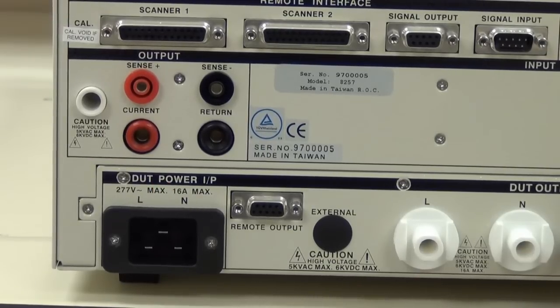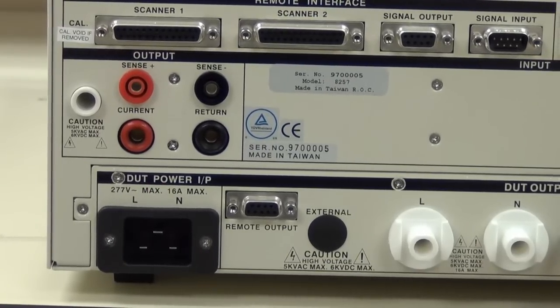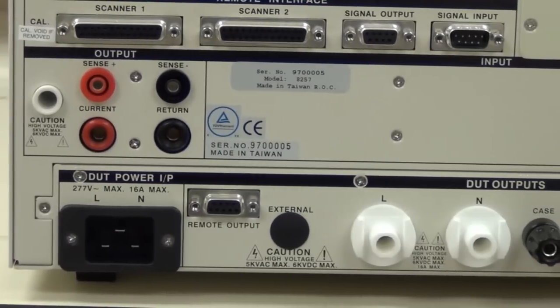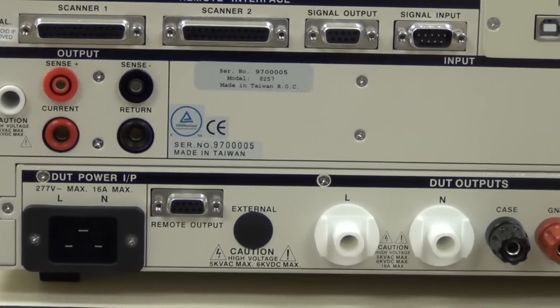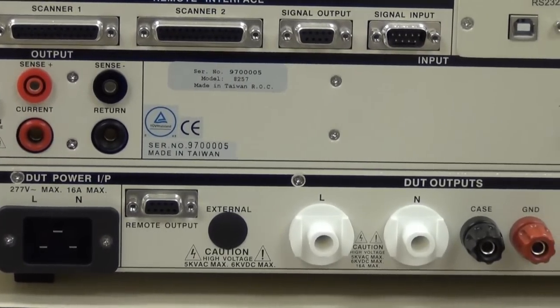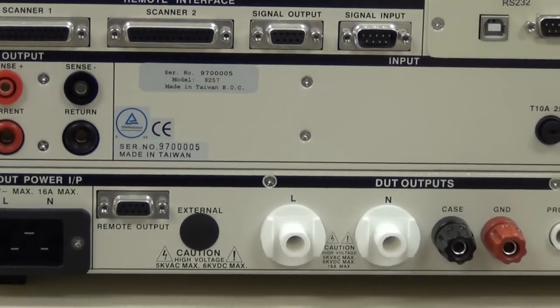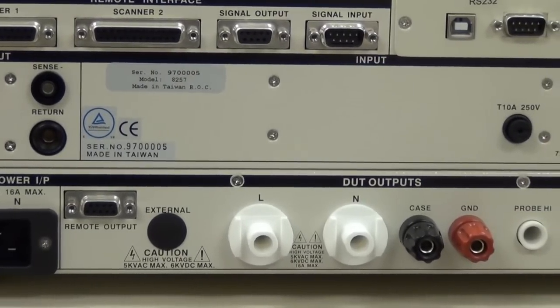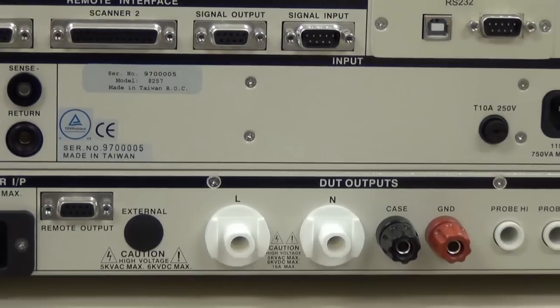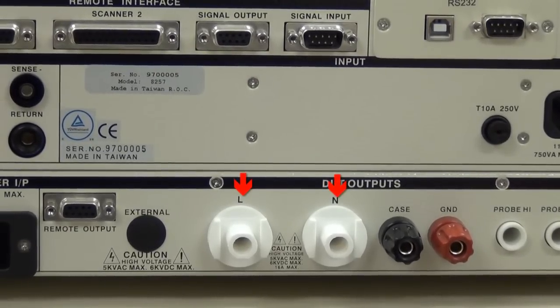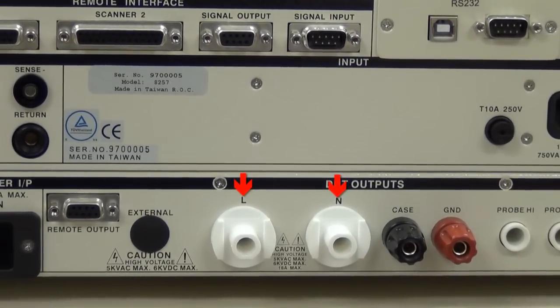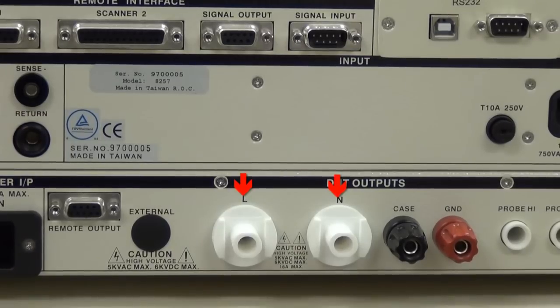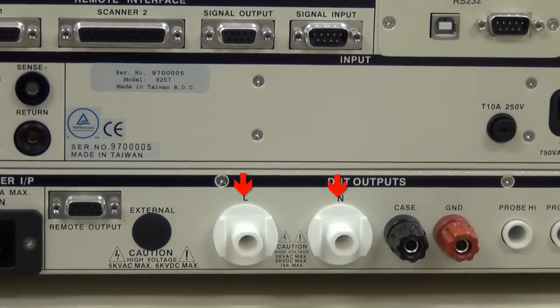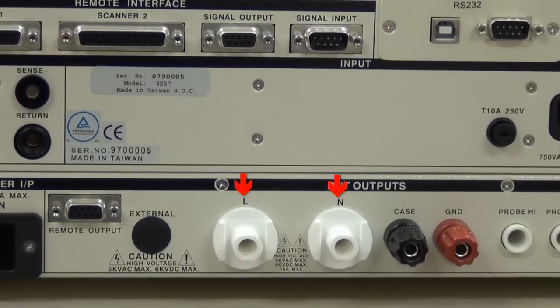The line and neutral output connectors are used to attach the adapter box high voltage test leads to the instrument. Line power is supplied to the DUT during the line leakage or functional run test through this connector, and high voltage is supplied to the DUT through this connector during the dielectric withstand or insulation resistance tests. During a dielectric withstand or insulation resistance test, the line and neutral terminals are shorted together.